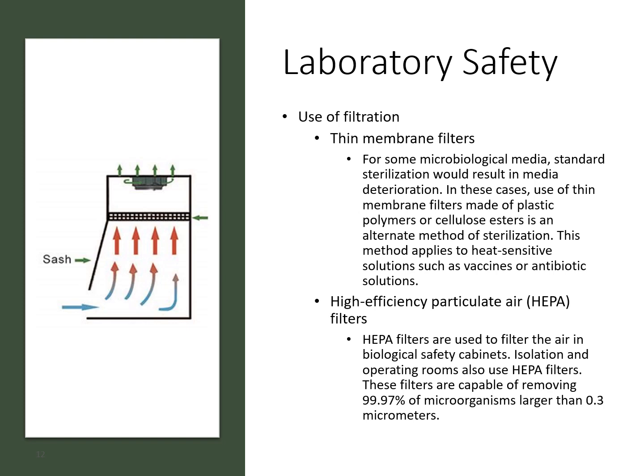HEPA filters are typically used in biological safety cabinets. The air flows in through the bottom under the sash, goes up through the top, passes through the filter, and is circulated either outside or back into the room. This type of filter will typically remove about 99% of microorganisms that are larger than 0.3 micrometers.